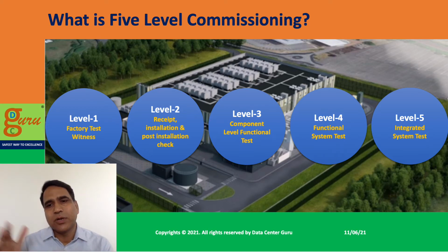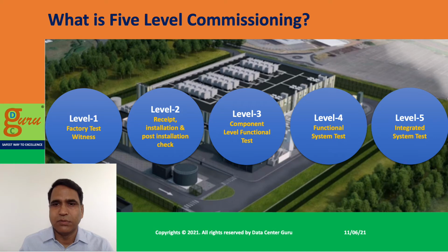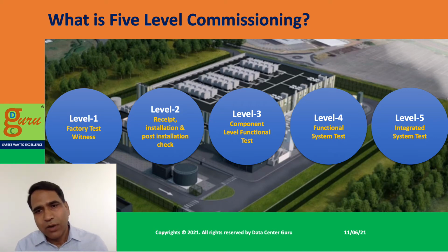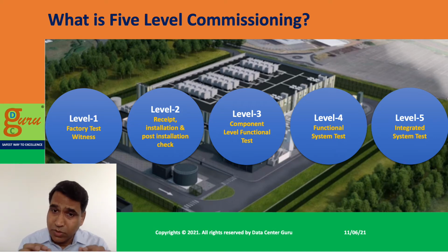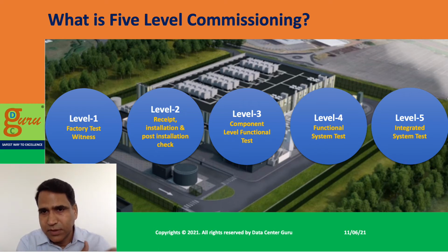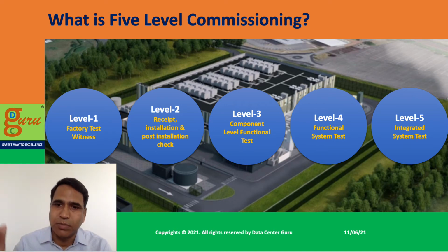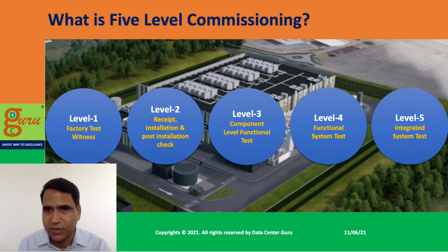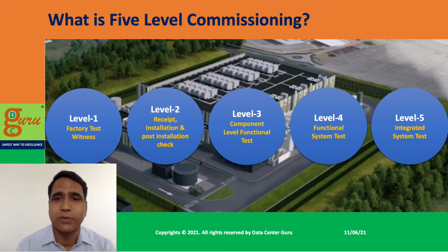Similarly, you have got other systems - cooling, safety, security - these are all the building blocks I talk about. So broadly, if you talk about a data center, you have got capacity components like UPS, cooling, and distribution paths - bus bars, panels, transformers, connectors. Each and every component at the nuts and bolts level has to be checked for performance.